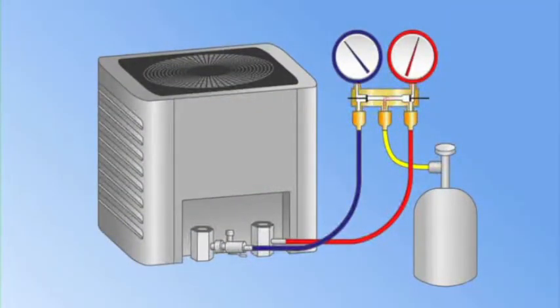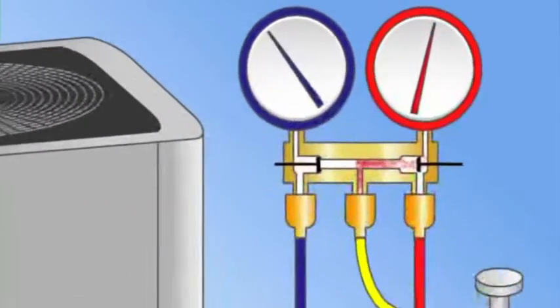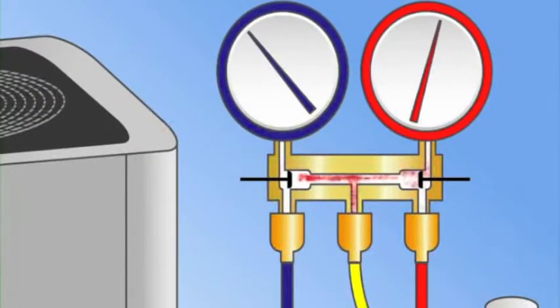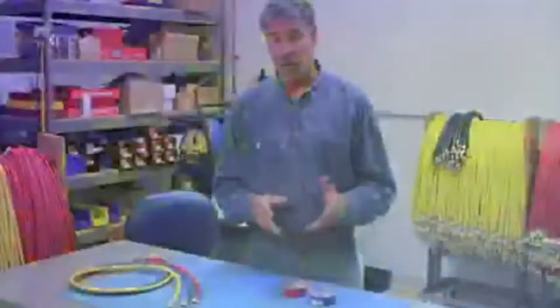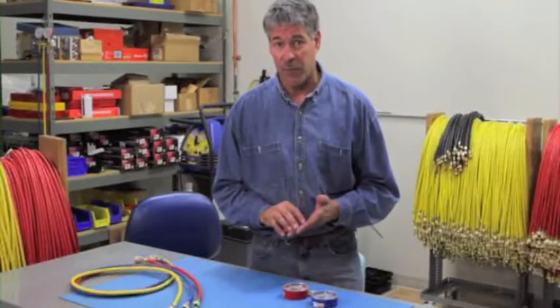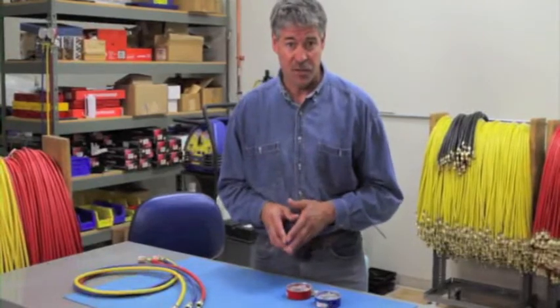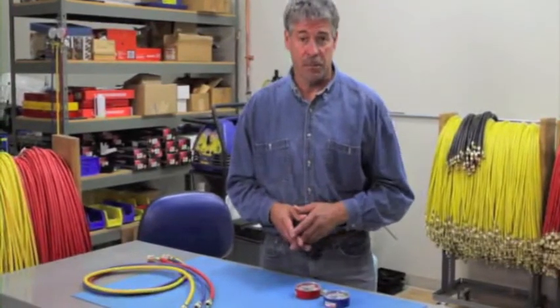Hi, it's Paul again. Overpressurization can occur when the manifold hoses are connected to a system in reverse or when high side system pressure is suddenly released to the low side through the manifold. This can also happen if you're using a manifold to read nitrogen test pressures or when the pressures are reversed in a heat pump.